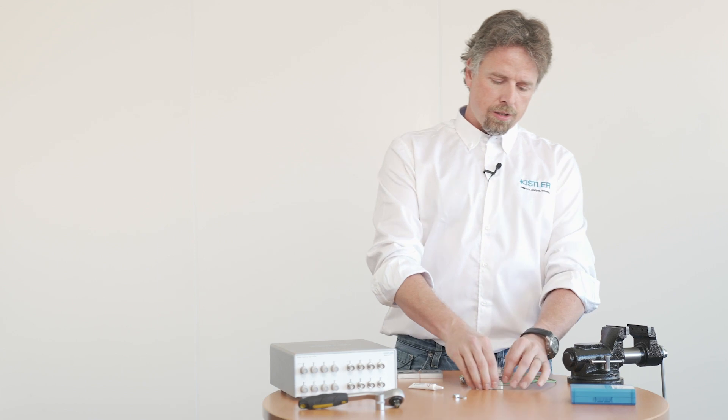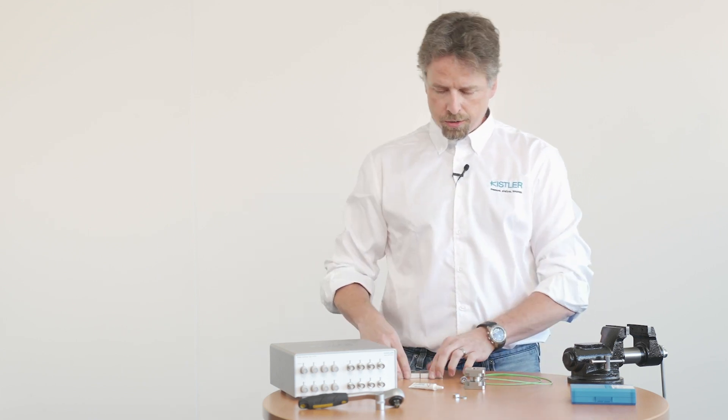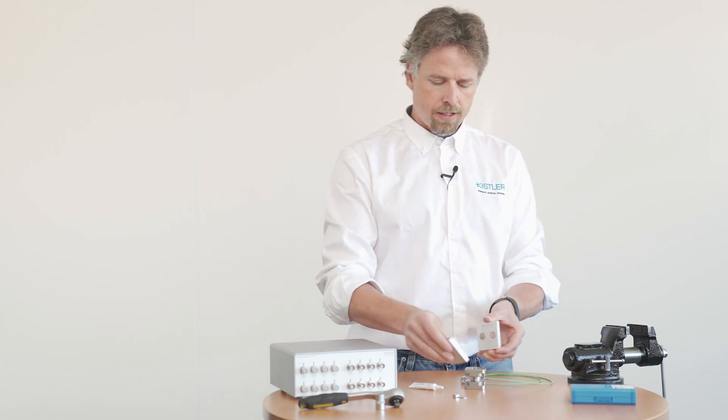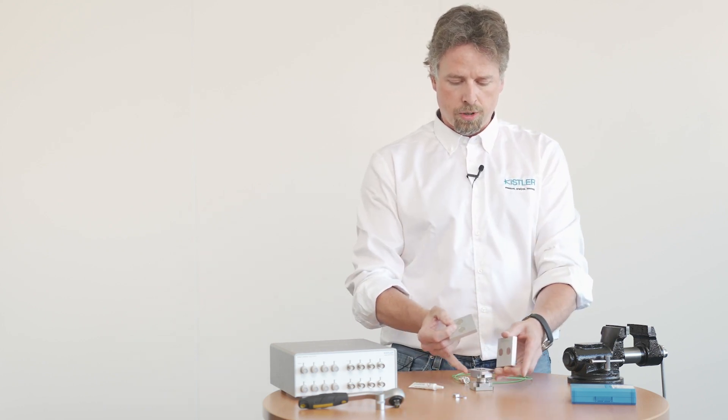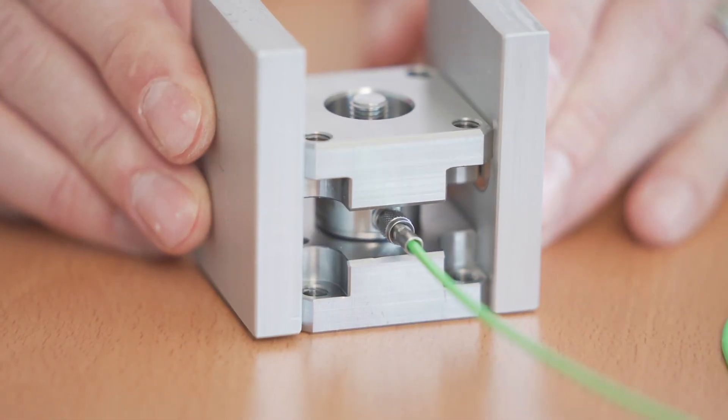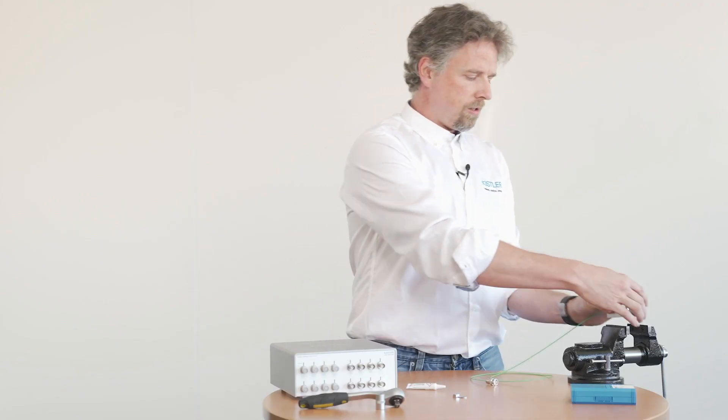In case alignment is a topic for you, then you can use the plug of the sensor in order to align. And here in our production, we use these two plates and we attach it to top and bottom plate like this.